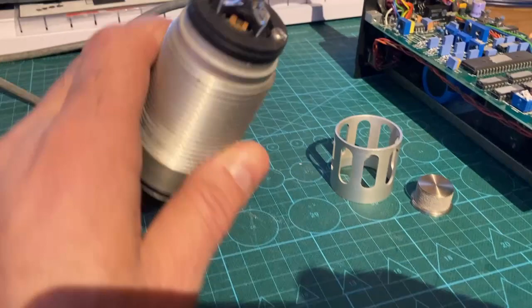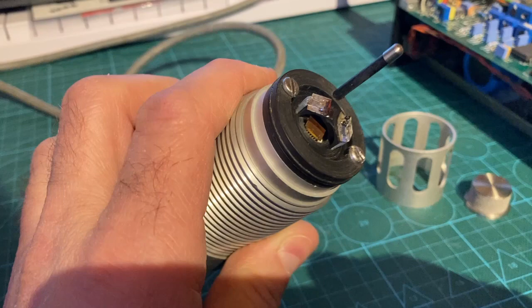So here's the probe. I've removed the little guard here and the filter cover from the probe, and you can actually just about see that shiny gold mirror there. So this is a type of hygrometer called a chilled mirror hygrometer, and that mirror is mounted on a Peltier device which can both heat and cool the mirror. And what it does, it cycles through heating and cooling the mirror, and when it's on its cooling run, it will detect when water vapor from the air condenses on that surface.